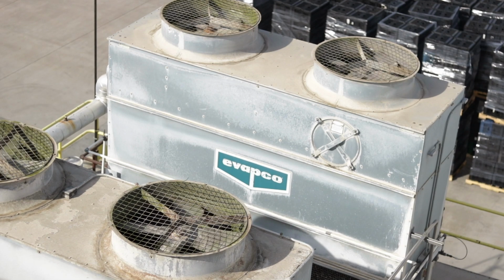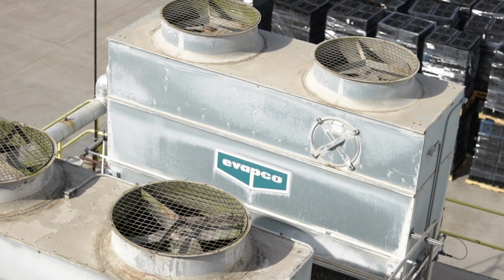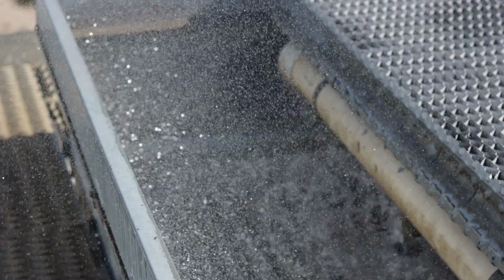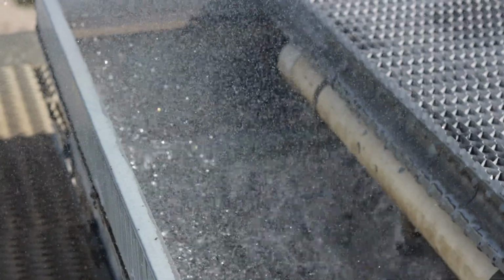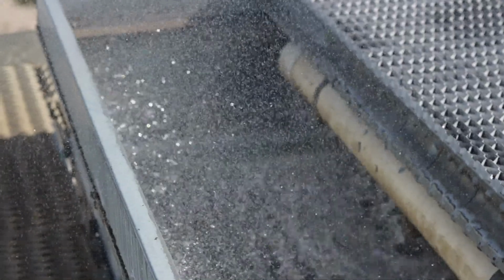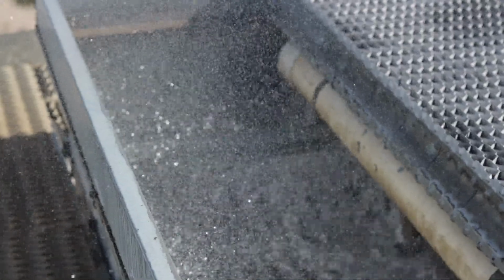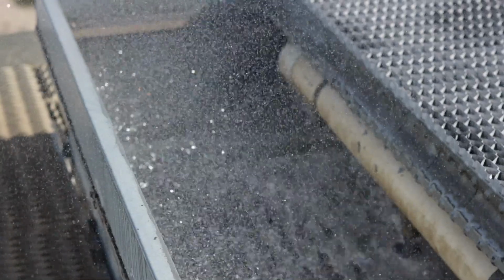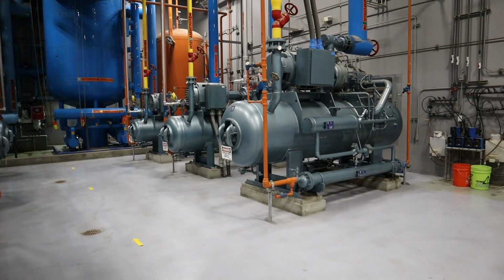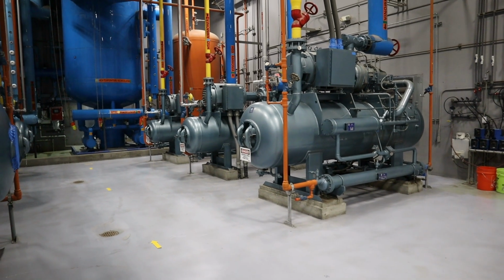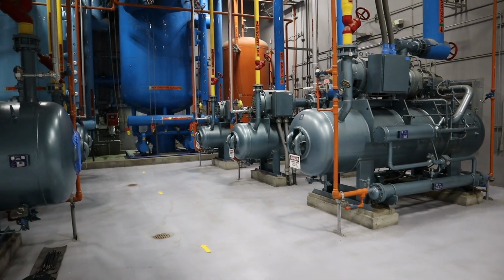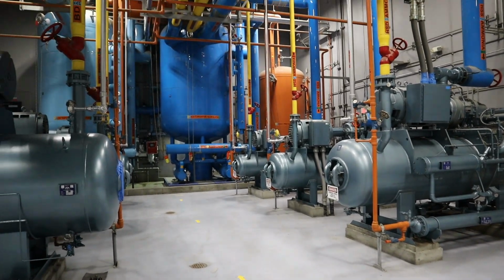Once the lubrication system has been verified, the operator must ensure that the condenser is running. Most ammonia refrigeration systems utilize evaporative condensers, which means the operator must verify the condenser fans are running and the water distribution system is operational. A compressor must not be started without adequate condensing capacity or high discharge pressure will ensue.